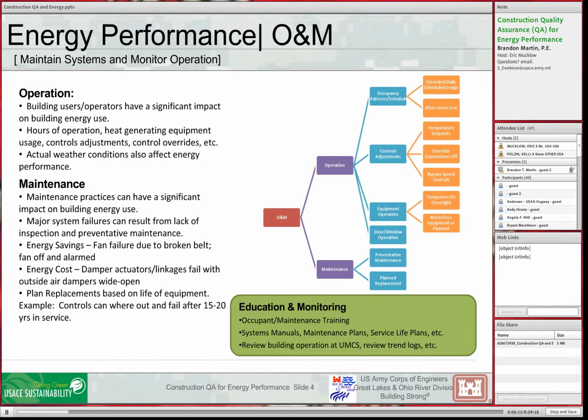I've actually walked into a mechanical room where an outdoor air system was not functioning because the fan belt had been broken. Nobody had been out to fix it. So that building is actually saving energy. It's probably not very comfortable or healthy.